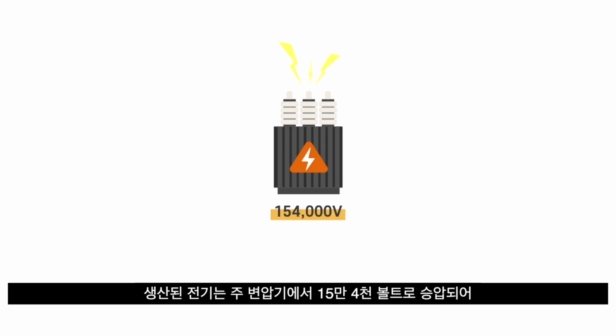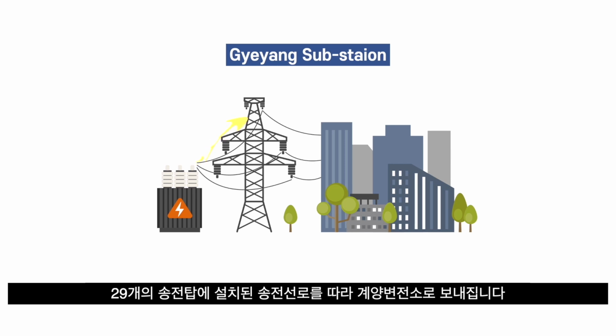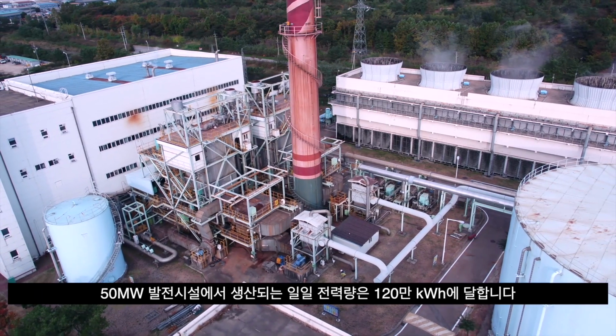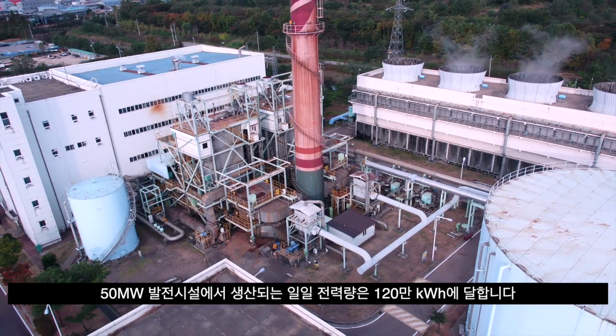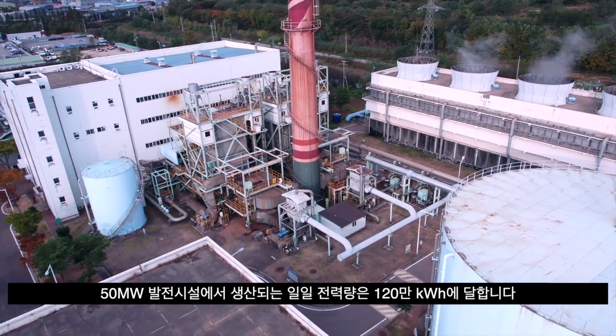The generated electricity is boosted to 154,000 volts through the main transformer and sent to the Gyeyang substation along the transmission lines installed in 29 transmission towers. 1.2 million kilowatt hours of power is generated per day by the 50 megawatt plant at SLC.